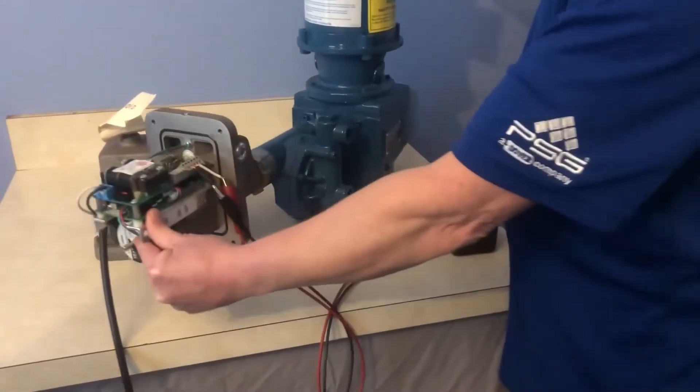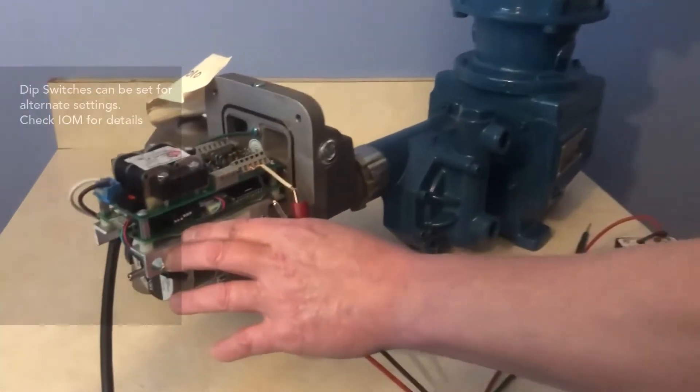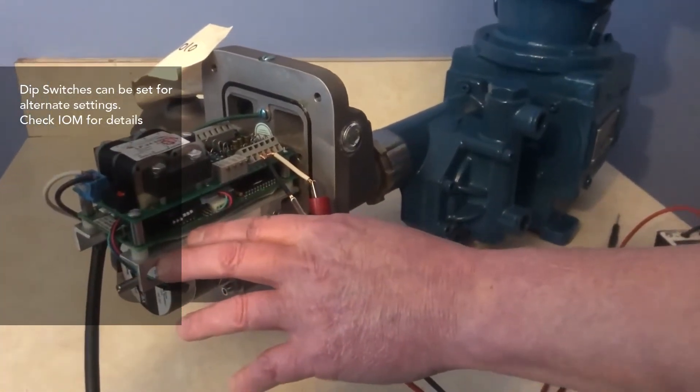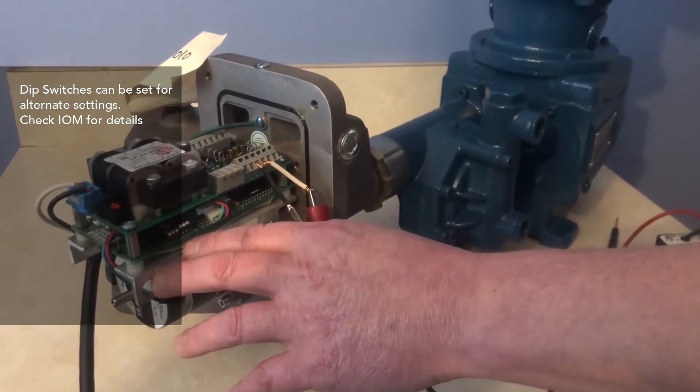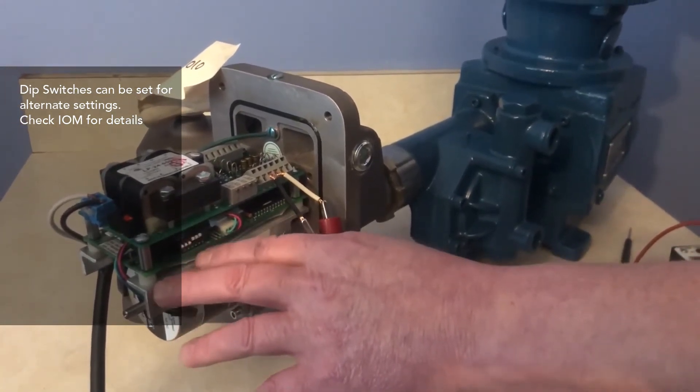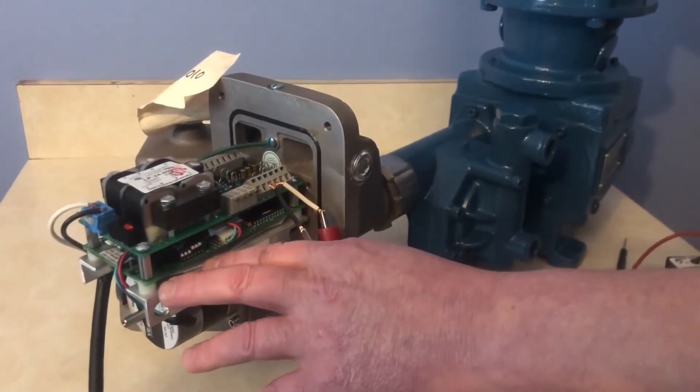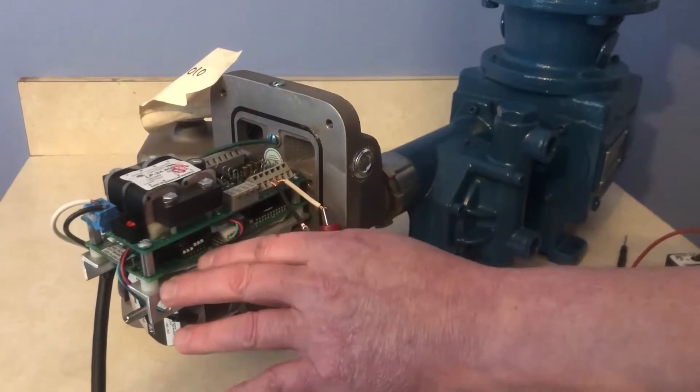Over on this side, you'll see dip switches. Dip switches are already preset from the factory for four milliamp being zero point or zero stroke on the pump, or 20 milliamps, which is the maximum or the max flow on the pump.